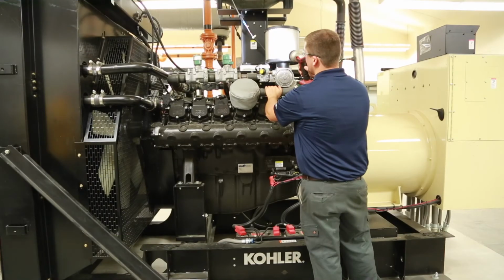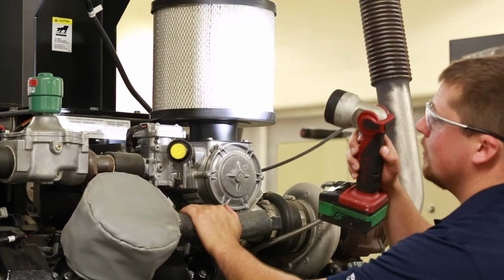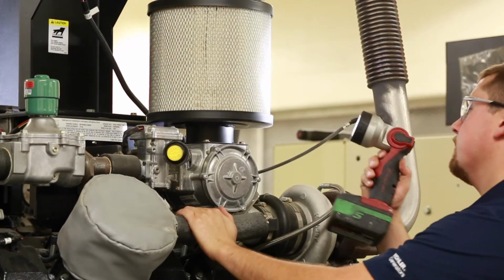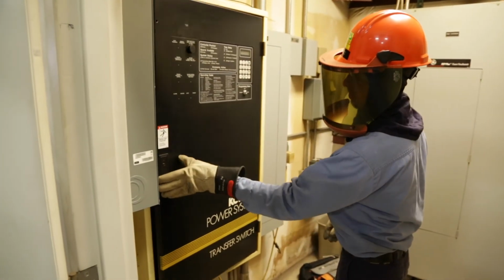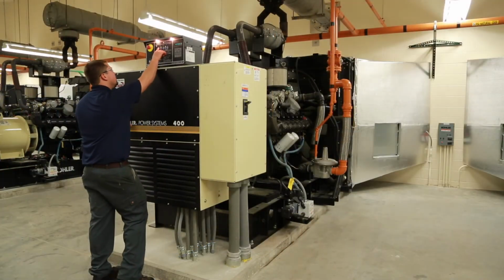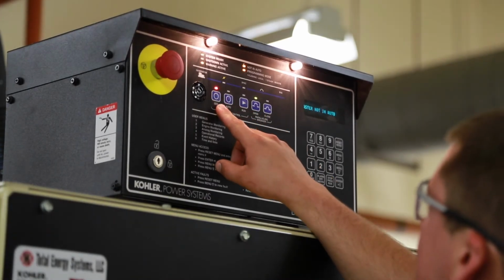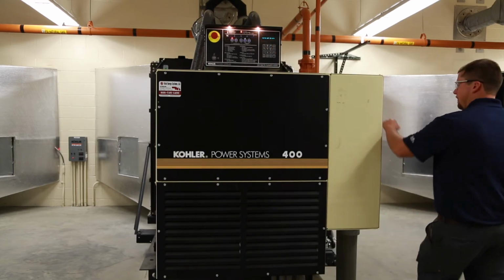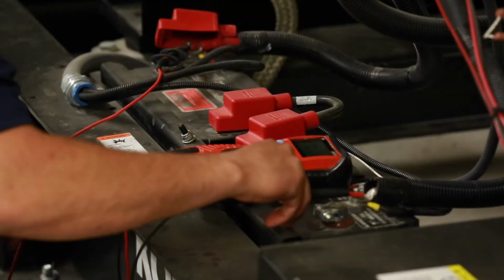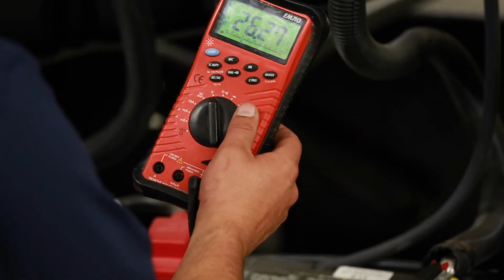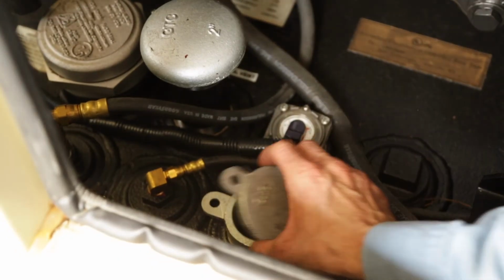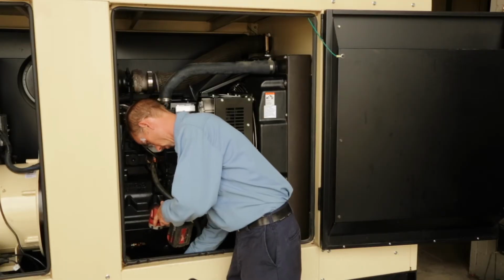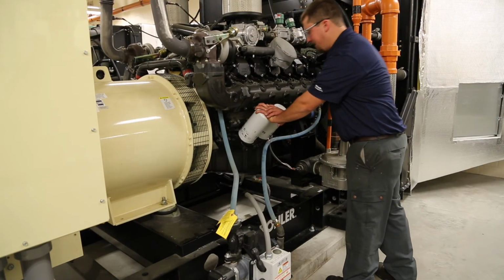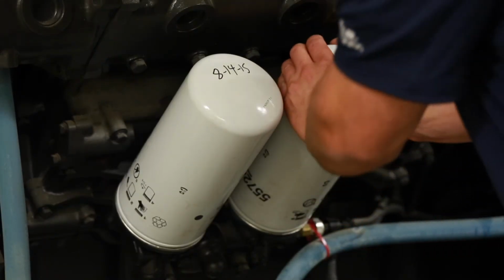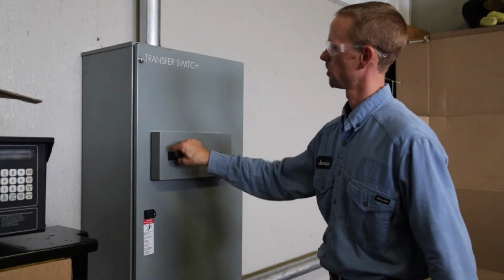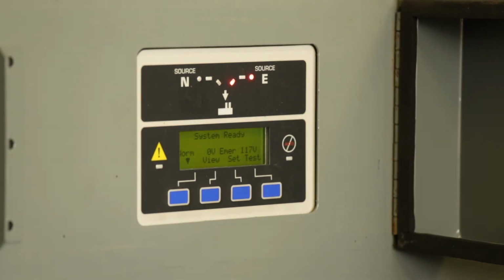Another reason for standby systems failing was poor maintenance. Kohler distributors see one of their primary services as providing planned maintenance to owners of standby generator systems. FEMA recommends planned maintenance programs for generator systems to ensure critical components within the system do not fail when the utility power drops out. Batteries should be checked and be connected to automatic battery chargers. Fuel tanks should be maintained full and fuel quality inspected with diesel fuel polishing. Air, fuel, and oil filters should be changed as dictated by the manufacturer. Electrical panels and transfer switches should also be checked to ensure they are in a state of readiness when the utility fails.